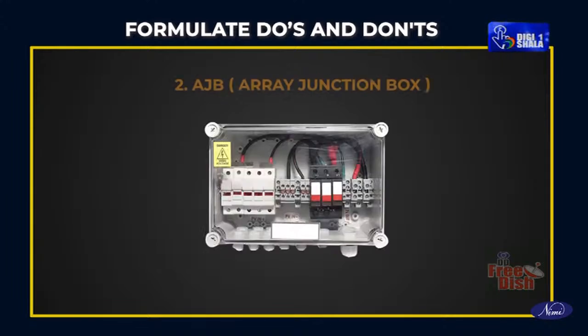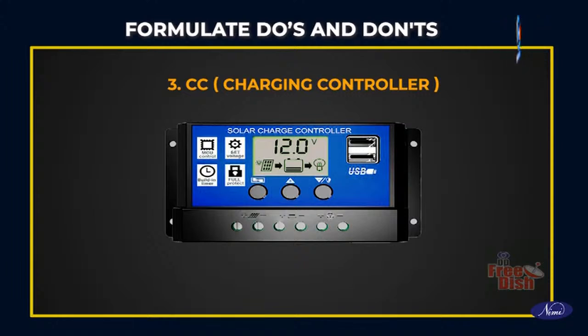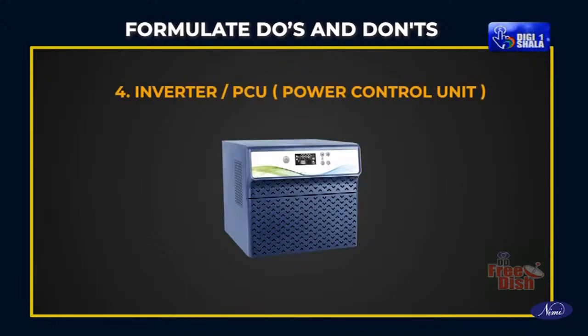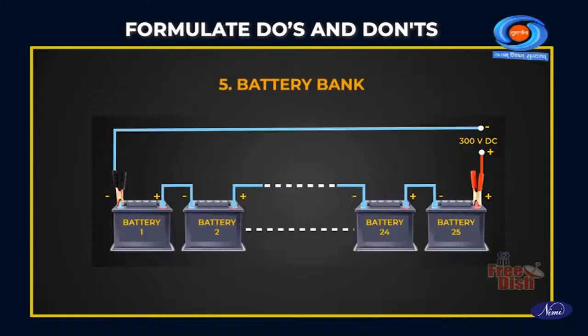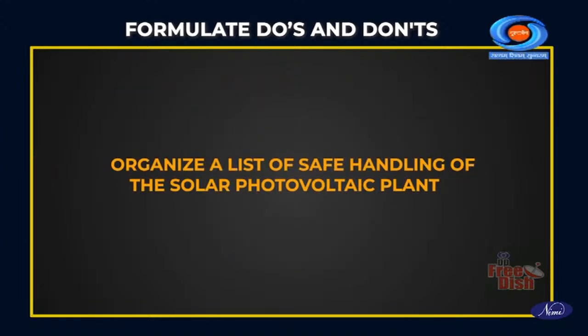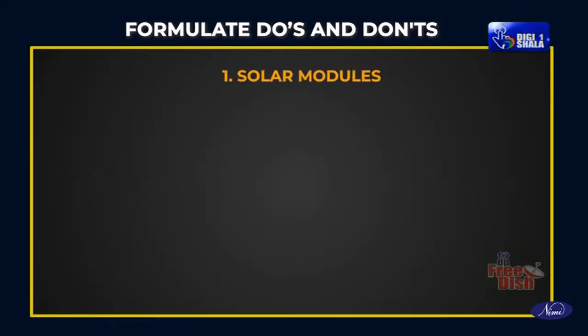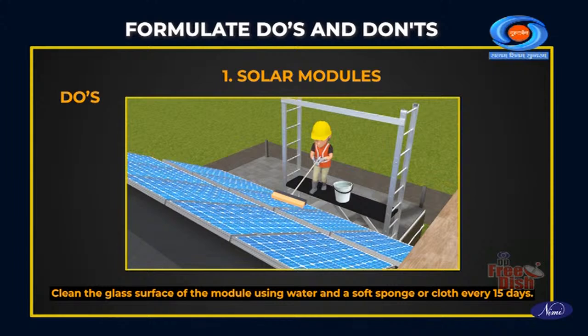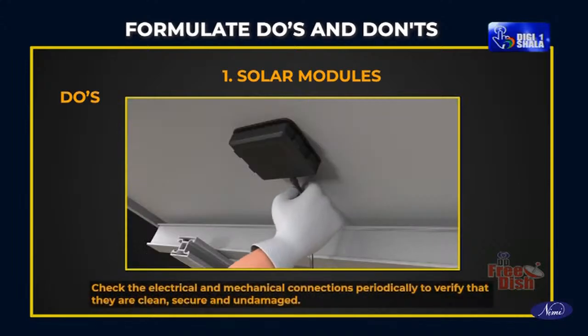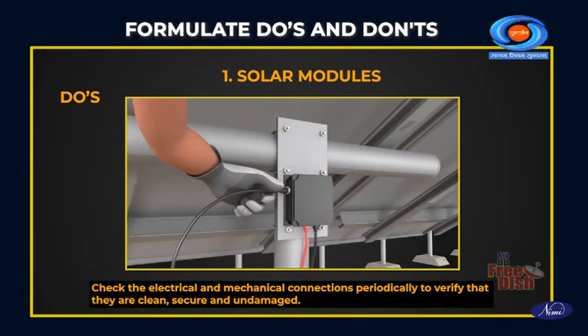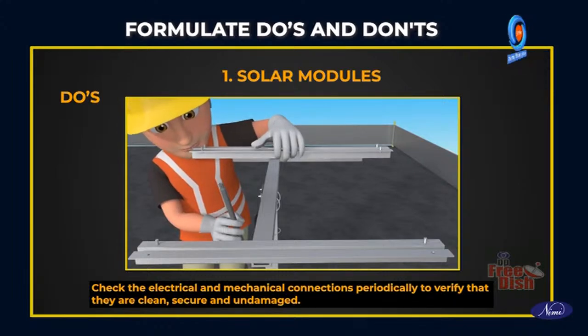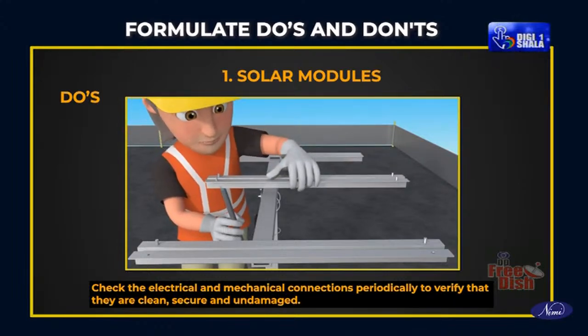The list of do's and don'ts covers solar modules, AJB (array junction box), CC (charging controller), inverter or PCU (power control unit), and battery bank. Organize a list of safe handling of the solar photovoltaic plant. Solar modules, do's: Clean the glass surface of the module using water and a soft sponge or a cloth every 15 days. Check the electrical and mechanical connections periodically to verify that they are clean, secure and undamaged.